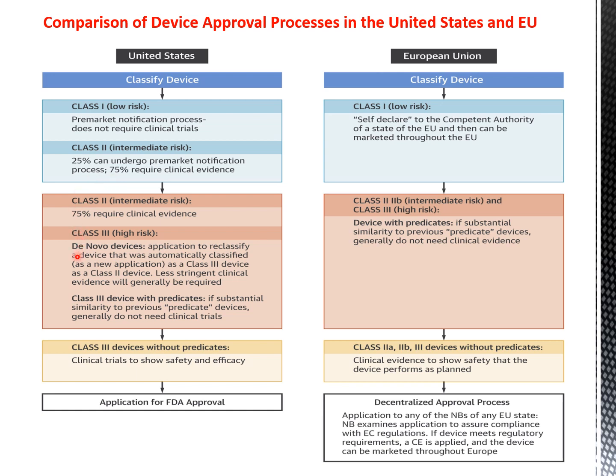And for Class 3, here the process is more stringent for the Class 3 or high risk devices. Clinical trials are required to show safety and efficacy. For Class 3 devices without predicates, clinical trials are required to show safety and efficacy. And for Class 3 devices, for the reclassification of a device that was automatically classified as Class 3 to Class 2, in this case, less stringent clinical evidence will be generally required.